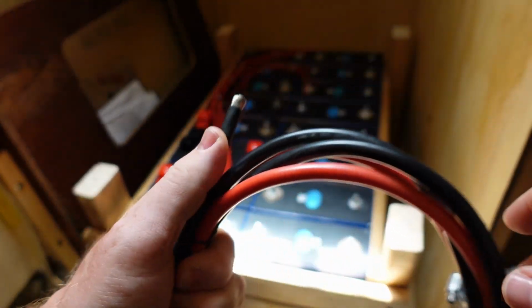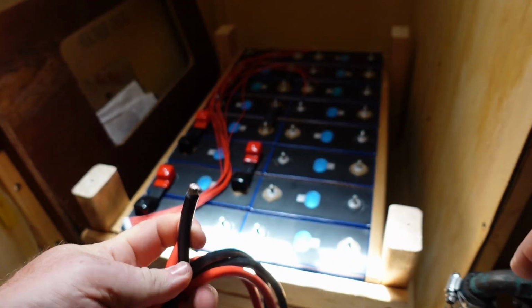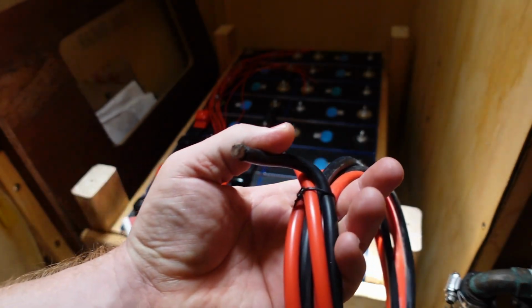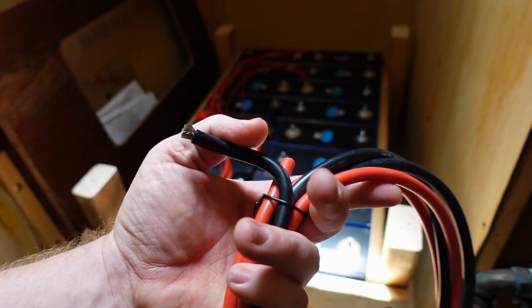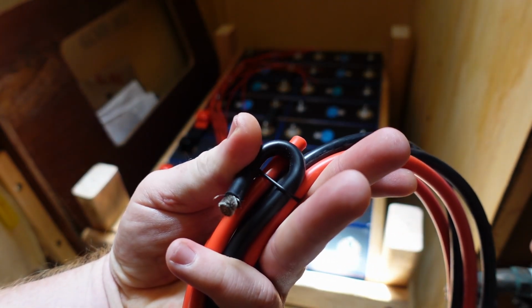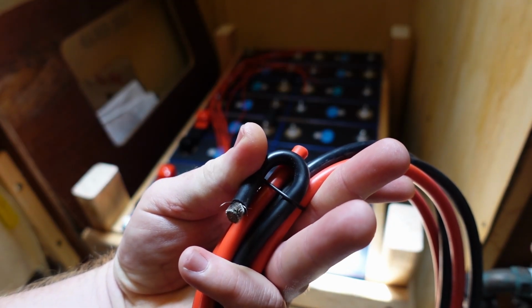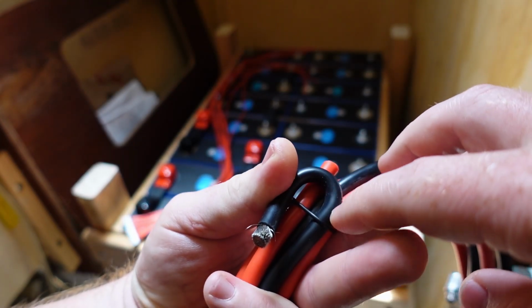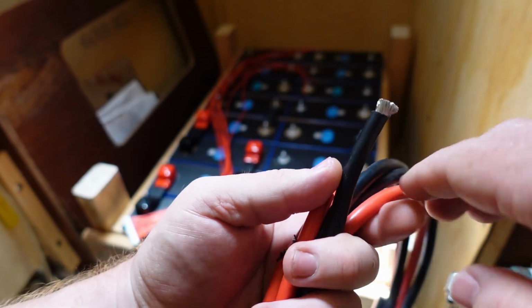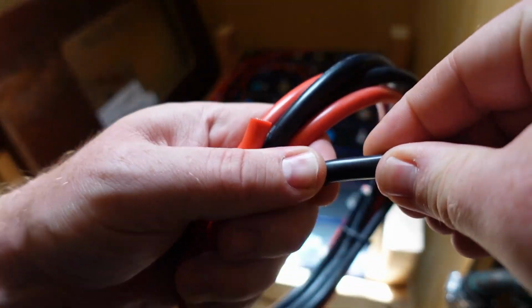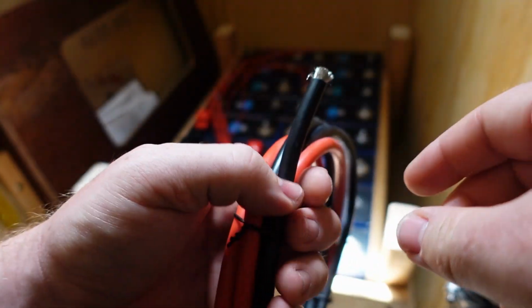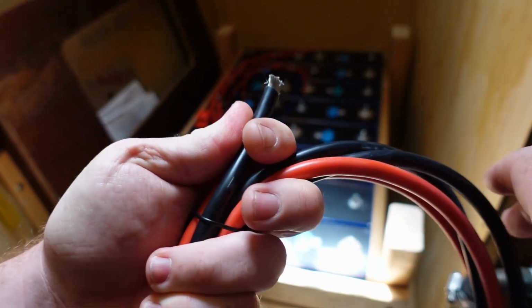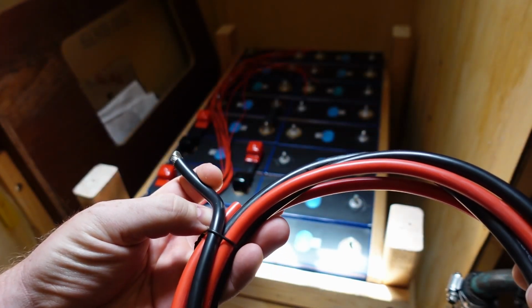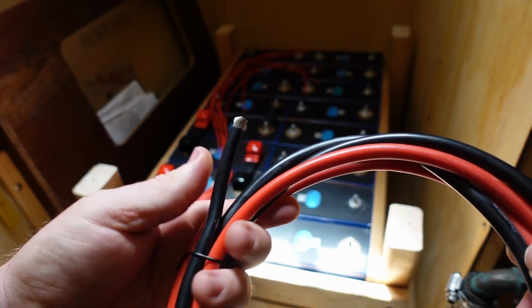Back to what I forgot to mention about this wire - the reason it's so good for this project is the bend radius. See this 6 gauge wire? I'm not even putting much pressure on my thumb to bend it. That wire is happy to do that, and it's capable of dealing with a lot more vibration and flex. It's also a much higher temperature wire, so it will survive a lot of things other insulations won't.